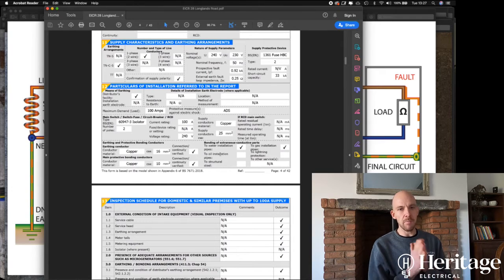We also check the size of the main earth coming into the consumer unit. It needs to be 16 millimeters squared. If it's any smaller than that, we need to investigate as to why that is. And the bonding conductors that we talked about before, which connect the other metallic services in your property, gas, oil, etc., back to the consumer unit, they need to be 10 millimeters squared. In older installations, they might be 6 millimeters squared, in which case that needs upgrading and needs looking into. So we just note all these values down and check them against what they should be.